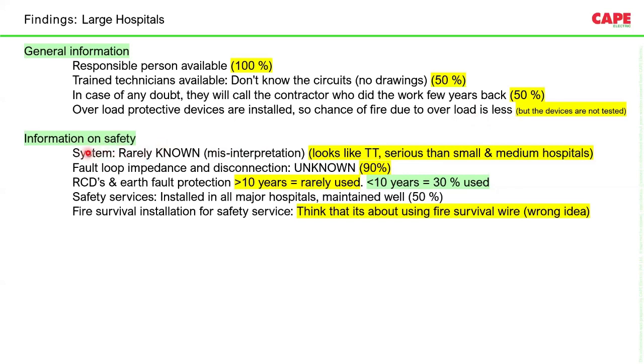With respect to information on safety in large hospitals, the system earthing like TN-S, TT, IT, the system earth is very rarely known and most often it is misinterpreted. Again, the system looks like a TT, but in a larger hospital this situation is even more serious than in a small or medium hospital. In a small or medium hospital, of course, the supply is LT, whereas in a larger hospital the system looks like TT but unfortunately is a very, very inefficient TN-S or TN-C-S kind of thing. Fault loop impedance and disconnection are unknown in more than 90% of cases.